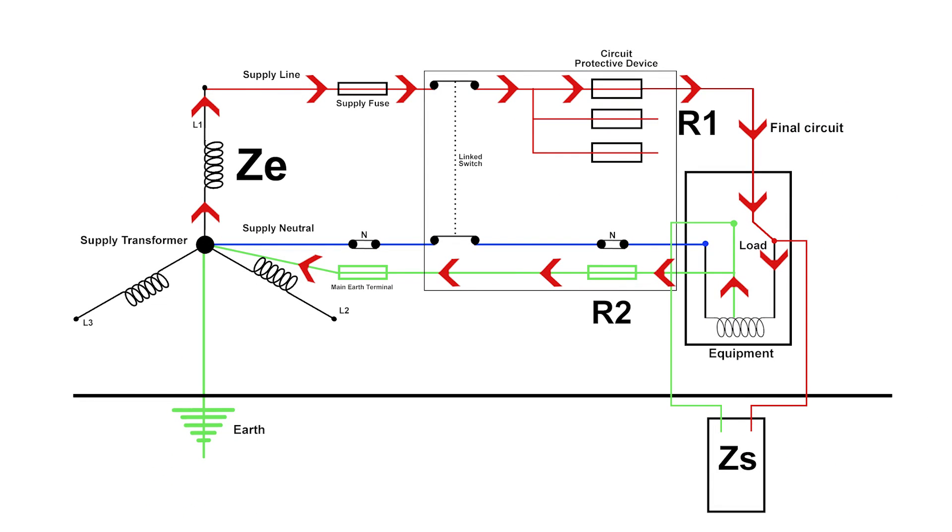The next component would be R1 and R2. R1 is the resistance of our line conductor. R2 is the resistance of our earth conductor. Ze plus R1 and R2 will add up for us to Zs. So that would be the complete system resistance through our earth, through the whole of the earthing system, back through the line conductor, back to our test instruments, which of course would be an earth fault loop impedance tester.